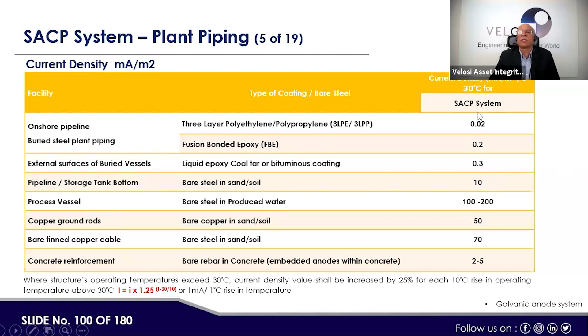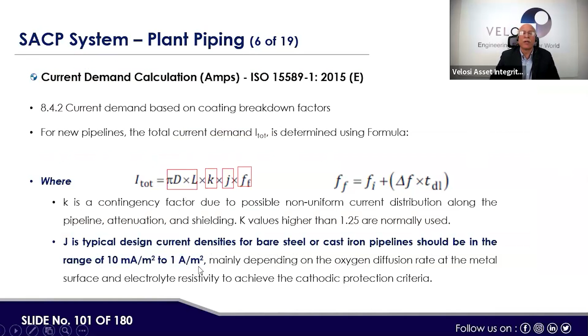So there are various current densities as per the SACP system. Then current demand is calculated with this formula, which summary is given earlier. Then J is the typical design current density for bare steel or cast iron pipeline, which should be in the range of 10 milliampere per meter square to 1 ampere per meter square mainly.